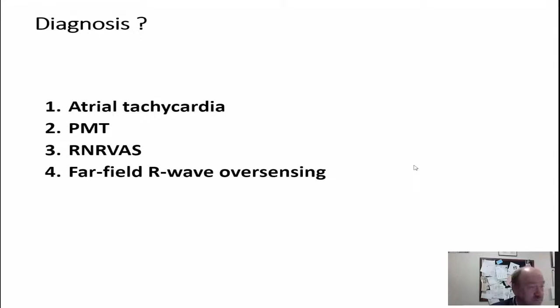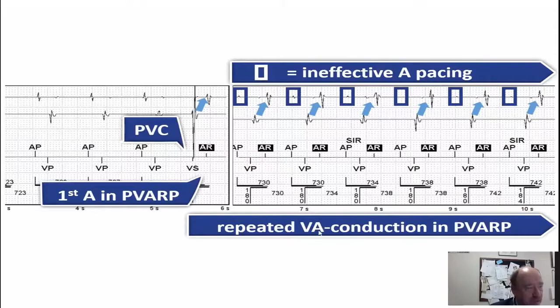The first beat falls in the patient's post-ventricular atrial refractory period. So we set up repeated VA conduction where the A falls into the PVARP due to functional non-capture. So the A is refractory, then the A pace is in the relative refractory period of the atrium. So we set up repetitive episodes of ineffective atrial pacing and repeated VA conduction where the atrium is in the PVARP. And I'll talk a little bit more about that.